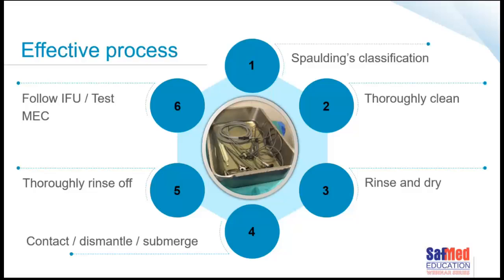To be effective, of course, the high-level disinfectant must make contact with all areas of the instrument or the device itself. Looking at the image in the middle over there, this was a urology list where high-level disinfection was being performed in this metal tub with a very small volume in it. You can see that the instruments and the devices were not properly submerged. They were never properly or fully covered. That's just silly.